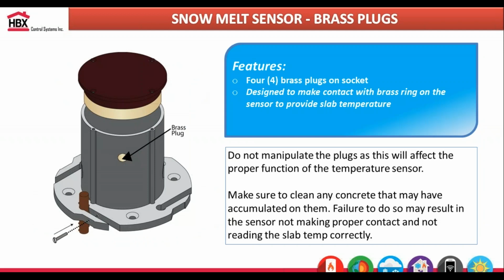In terms of the optical sensor as well, it'll tell the controller when it is actually snowing, and it will also feed back the temperature if you have it internally on there. There's a built-in thermistor in there. The sensor itself has a brass ring, and as you'll notice on the optical socket, there are 4 brass plugs. Once that brass ring makes contact with those four brass plugs, it'll feed the temperature back to the controller.